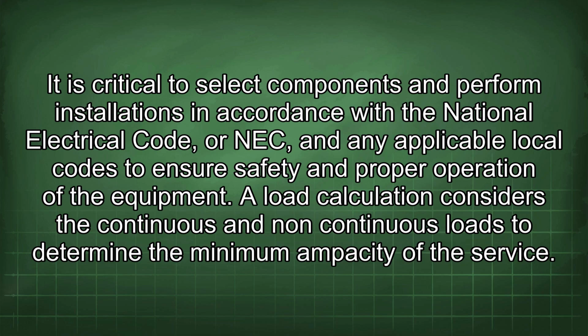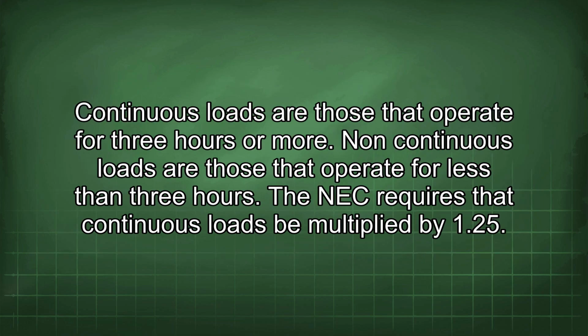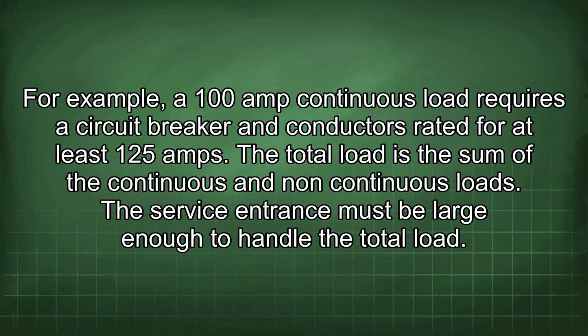A load calculation considers the continuous and non-continuous loads to determine the minimum ampacity of the service. Continuous loads are those that operate for 3 hours or more. Non-continuous loads are those that operate for less than 3 hours. The NEC requires that continuous loads be multiplied by 1.25. For example, a 100 amp continuous load requires a circuit breaker and conductors rated for at least 125 amps.